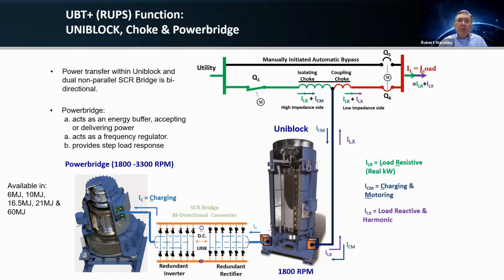So let's add energy storage to the component, because without energy storage, we don't have uninterruptible power for very long, do we? So in the Piller Power Systems our first choice is the power bridge, or the flywheel energy storage device. And we use that to provide energy buffer or ride through from an outage or an extended outage to get us to an alternative energy storage device. That could be another utility. It could be a generator, a multitude of alternative energy storage devices. We can give you those flywheel energy storage devices anywhere from 6 megajoules up to 60 megajoules, so that you have as much ride through and power as you need to make that transition, based on the topology of the system.